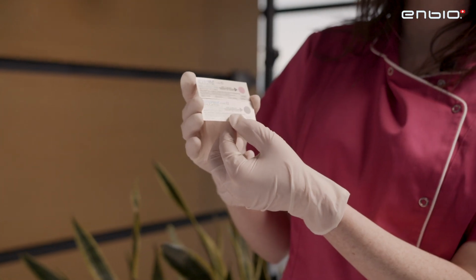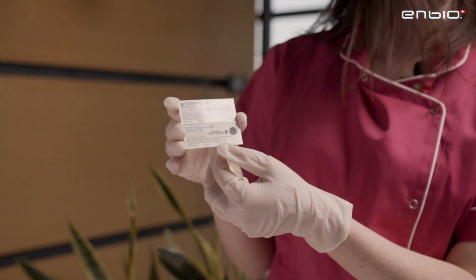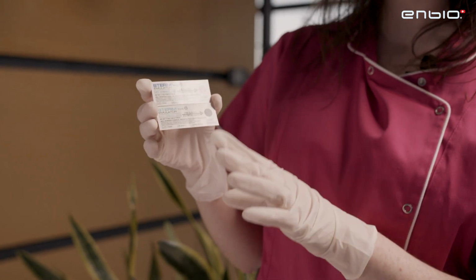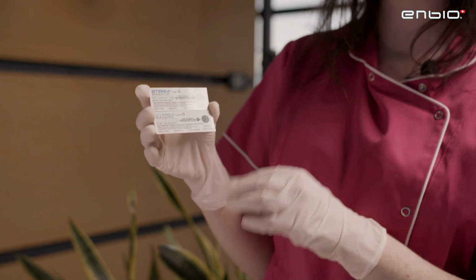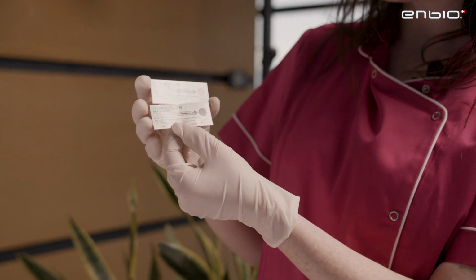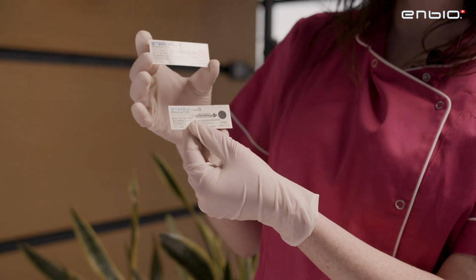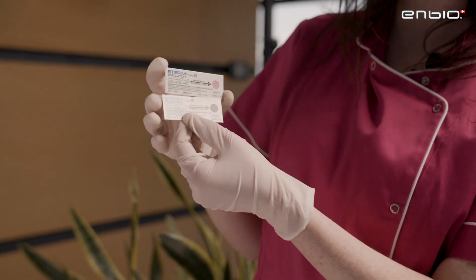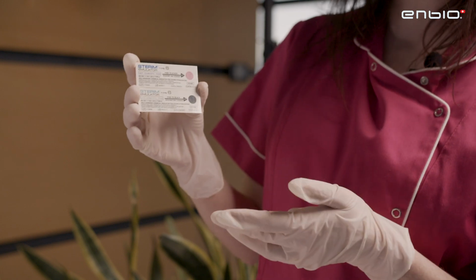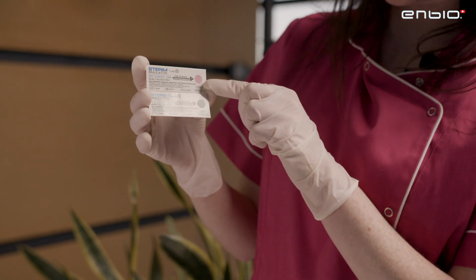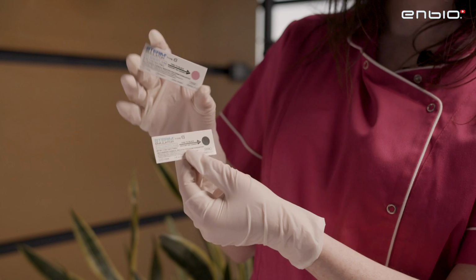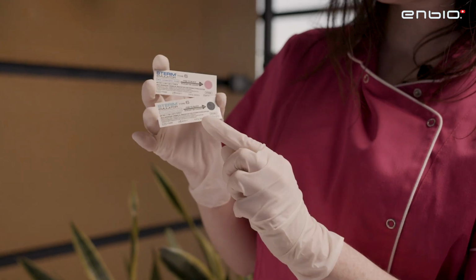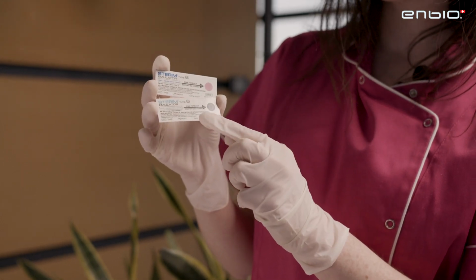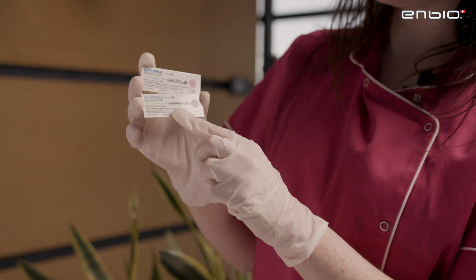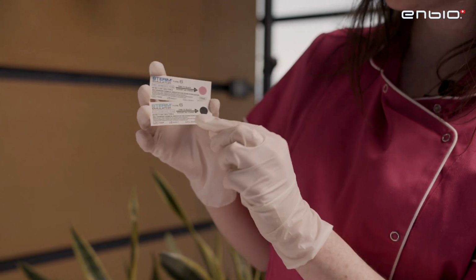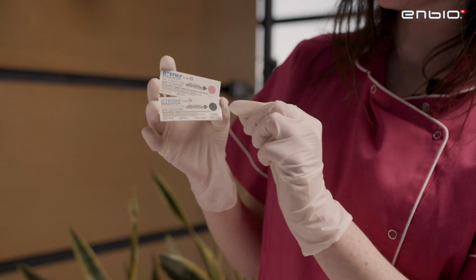So here we have the Class 6 chemical indicators, and we can see on them additional information on how to use them inside the autoclave. So for instance, this is a test that has not been used yet, and we can see that if the sterilization is successful, the color needs to change from pink to black. So here the color is still pink, but here we can see that this indicator confirms a successful sterilization process because it changed the color from pink to black.